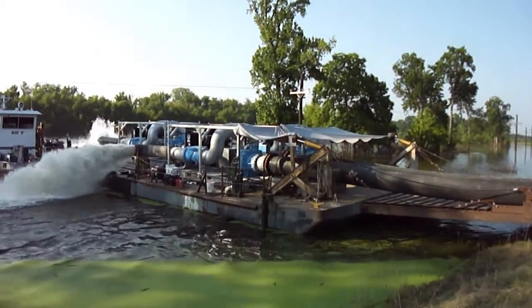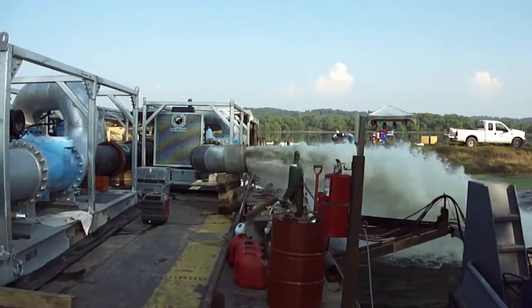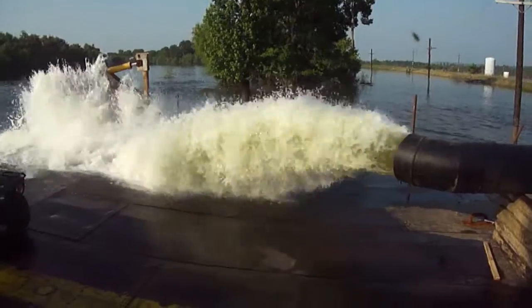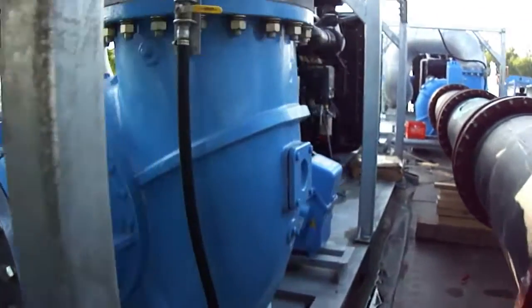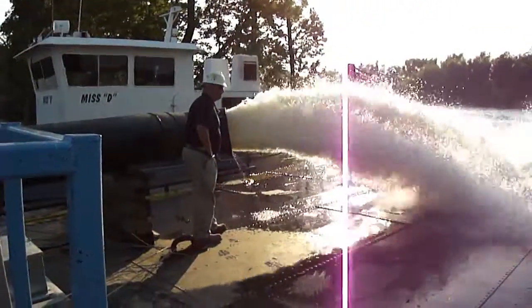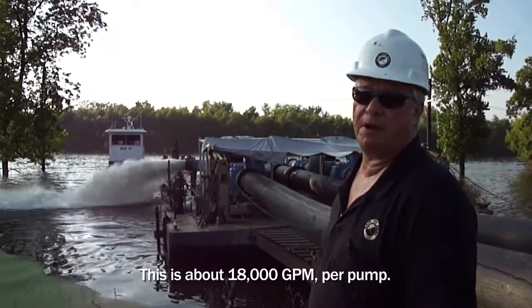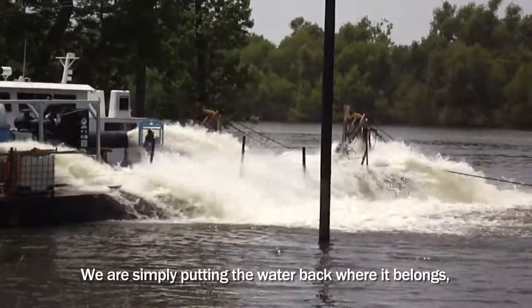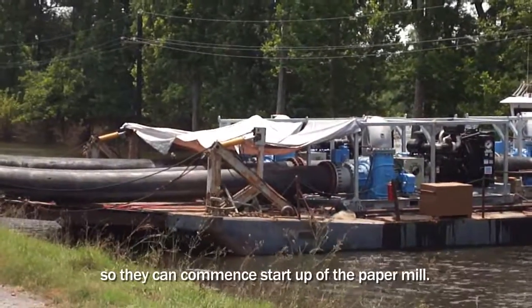Direct access to the ponds was blocked by floodwaters, so Rain for Rent engineered a unique pumping system to remove water. Three 24-inch pumps were put on a barge and ferried 25 miles down a flooded river. The barge system was able to rise and fall with the level of the river while continuously extracting water from the paper mill's holding pond — that's about 18,000 gallons per minute. All they were doing was putting the water back where it belongs so the mill could commence start-up.